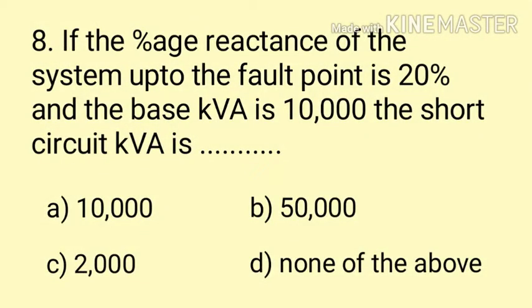Question number 8. If the percentage reactance of the system up to the fault point is 20% and the base KVA is 10,000, the short circuit KVA is dash. Isme dekho base KVA given hai 10,000, percentage reactance up to the fault point hai 20%. Short circuit KVA ka formula hai: base KVA × 100 / percentage reactance = 10,000 × 100 / 20 = 50,000. The correct answer is Option B.